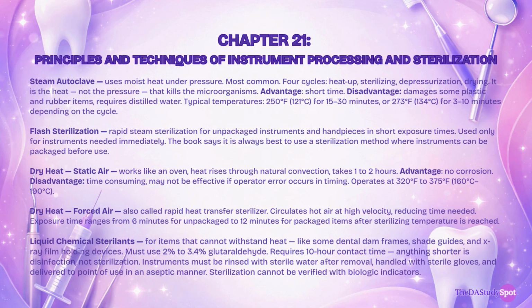Now, instruments must be rinsed with sterile water after removal, handled with sterile gloves, and delivered to point of use in an aseptic manner. But also keep in mind that sterilization cannot be verified with biologic indicators, so make sure you're going to that 10-hour mark. You can even go 12 or do it overnight.